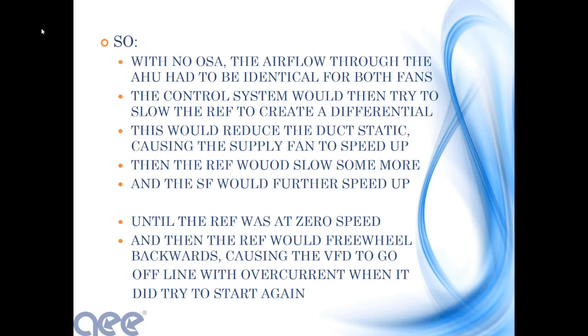So what happens? The control system is trying to slow the return exhaust fan to maintain a differential, but it can't do that. Next thing you know, the static pressure sensor out in the ductwork says, I don't have enough static, I better speed up the supply fan. And it sped the supply fan up. Now the return fan says, I need to slow down even more. Pretty soon we had the return exhaust fan at 0 speed, and it was freewheeling going backwards because the supply fan was sucking air through it.